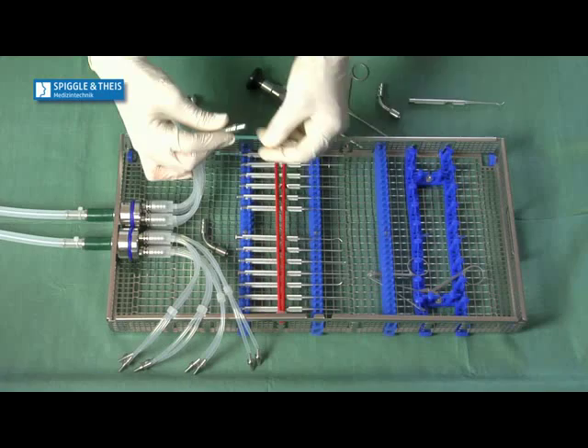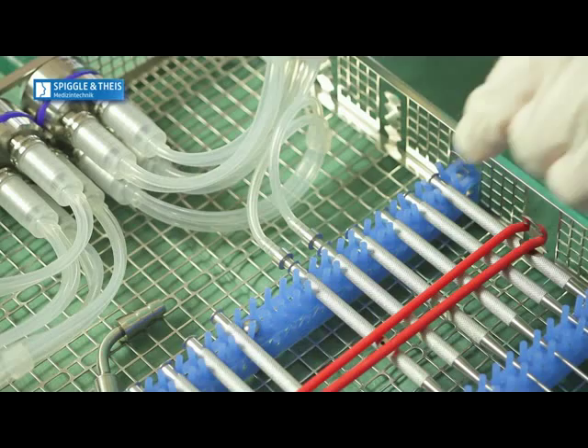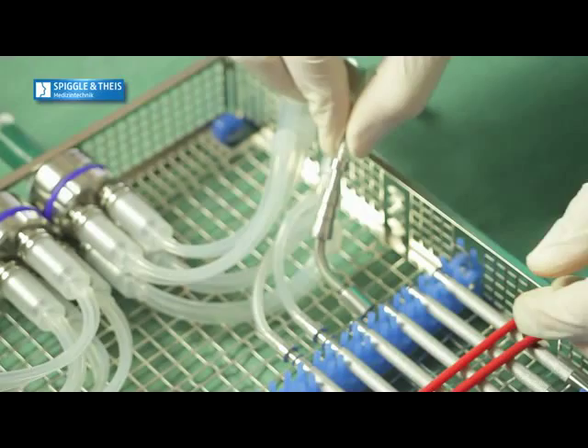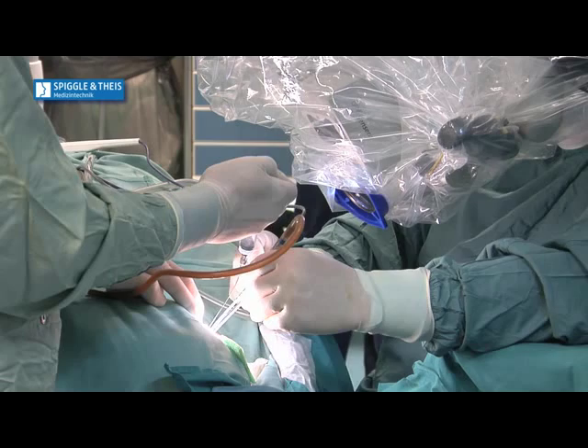In this scene, the assembly of the instrument's suction system is shown. You can see the connection of instruments to the angled junction. This junction is provided with a luer lock that allows fast change between different working ends that, once mounted, can be rotated 360 degrees on their own axis. The other end of this junction is then connected to the suction hose. The curved shape of this joint allows minimizing the friction offered by the suction hose.